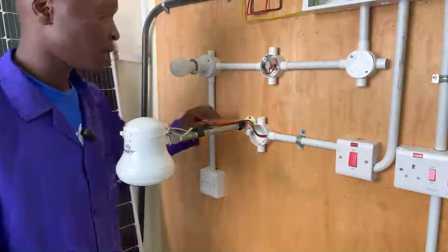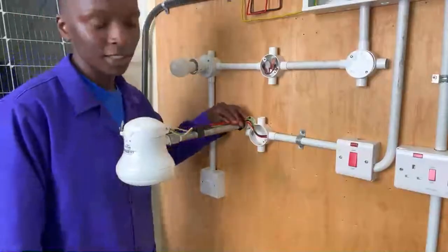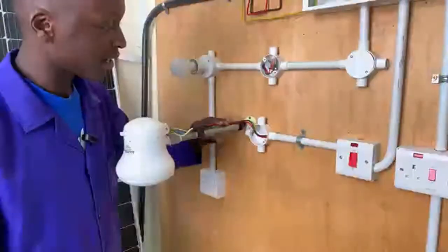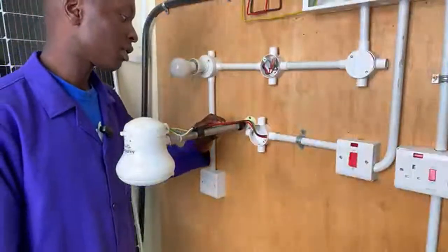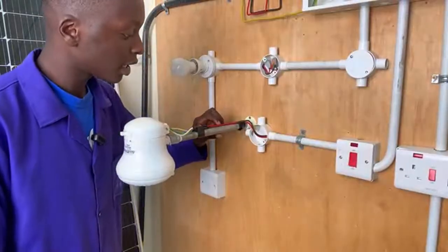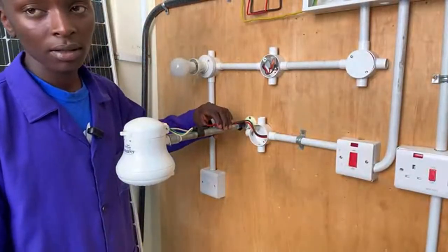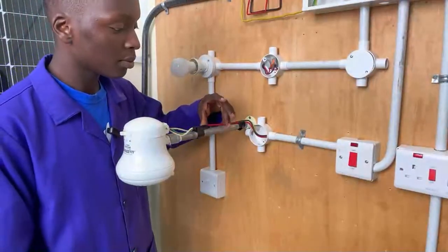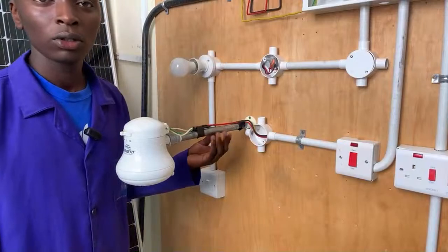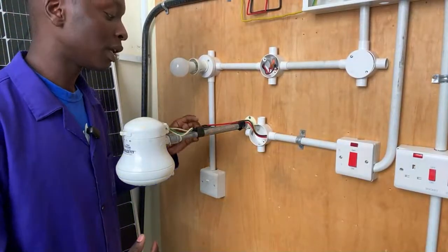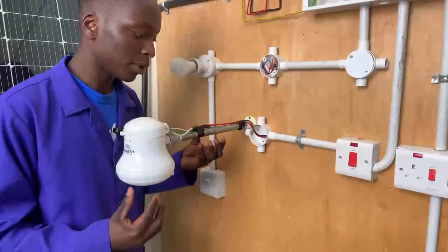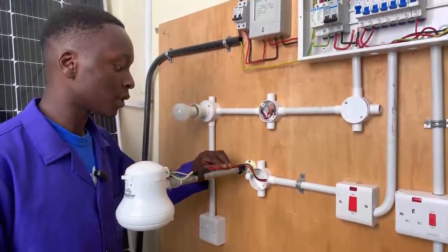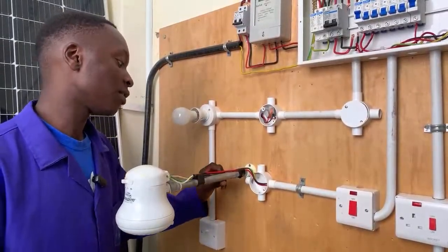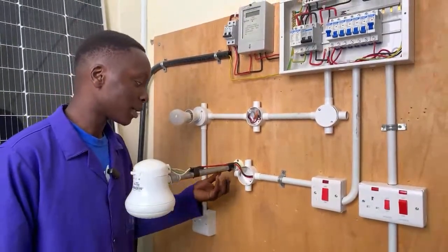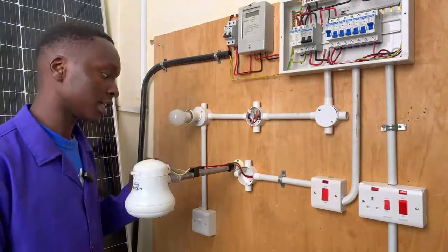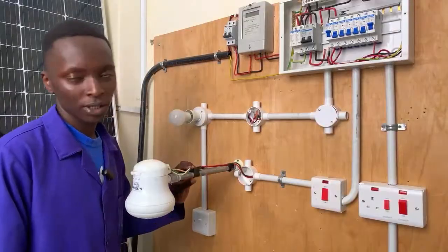The first thing is you can see these cables are just naked and wrapped in metal, which, if the cables have a naked point, can make this metal come into contact with the cable and cause a fault. Especially if it's alive, it may cause electrocution because water passes through the pipe and it will become charged. The other thing is about the joints.